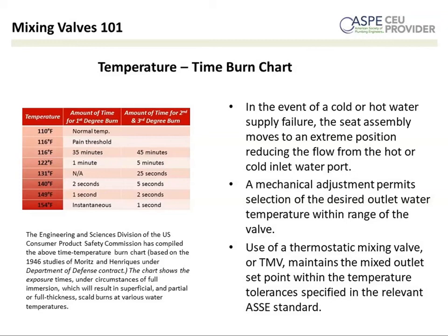Okay, another question. What if the power is out? How do you guarantee mixing? Do you need a backup UPS and a backup battery? So it works a little different with different mixing valves. If you lose power, in the case of some, you go to full cold. So that protects against it, it completely shuts off the hot water. And in that event, there's a manual override. Once you go to full cold, you can actually go down to the unit, and on the actuator, you can press a button and manually set the valve, if there's a power outage and you don't have a battery backup system. So there are some safety nets in place to help you until the power returns. But obviously, we recommend whenever you can put it on a battery backup, that would be ideal.